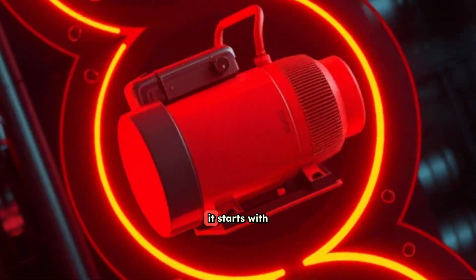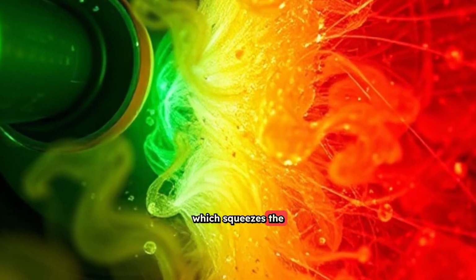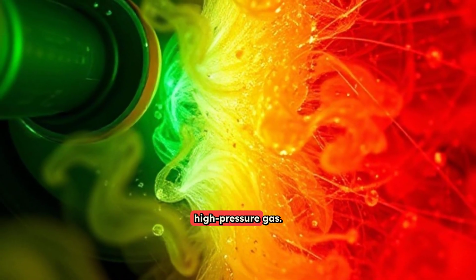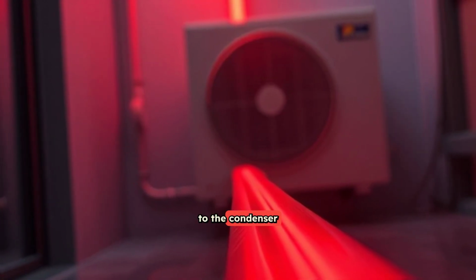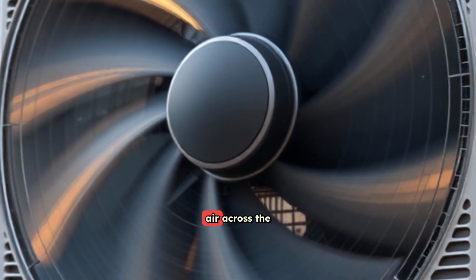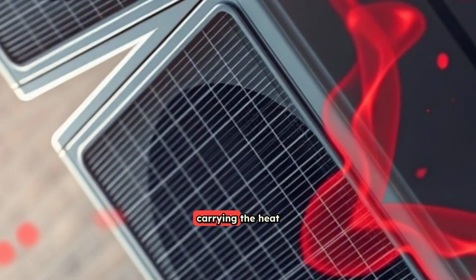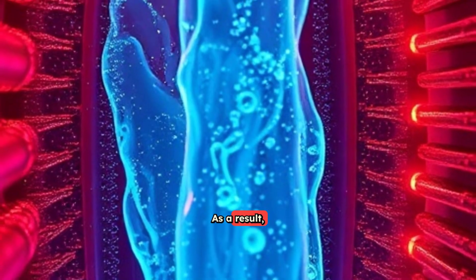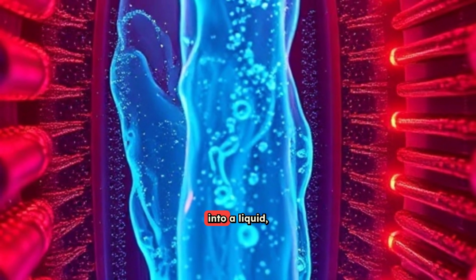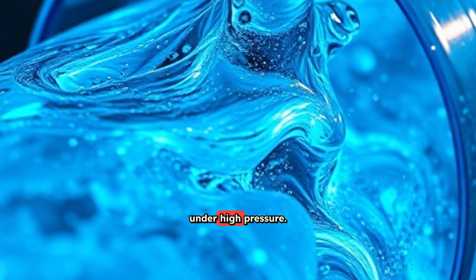The cooling cycle. It starts with the compressor, which squeezes the refrigerant into a hot, high-pressure gas. This gas flows to the condenser outside. A fan blows air across the condenser's metal fins, carrying the heat away. As a result, the refrigerant cools down and turns into a liquid, though it's still under high pressure.